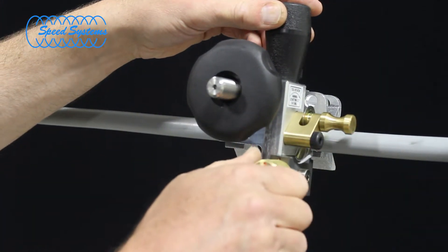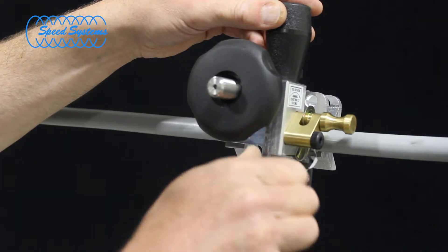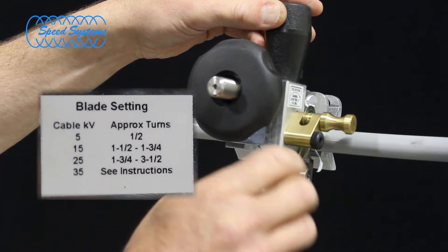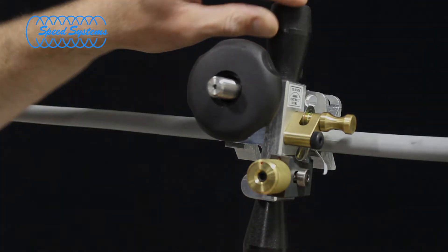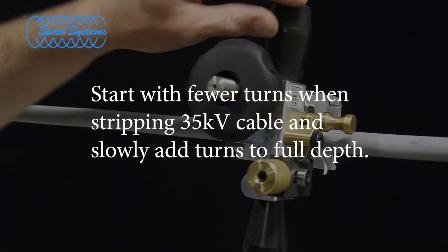Set the blade depth using the blade adjuster knob. The chart on the nameplate provides an approximate setting based on the kV rating of the cable. For 35kV cable, start with fewer turns for the first revolution and gradually increase the depth of cut to lessen the risk of twisting the conductor.